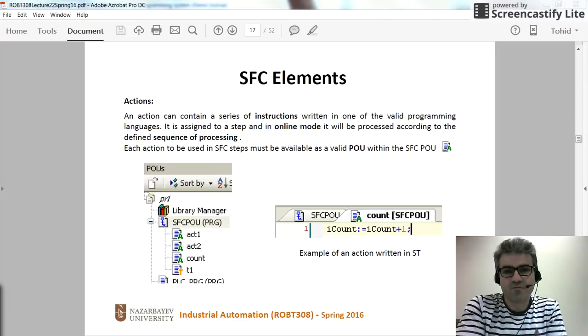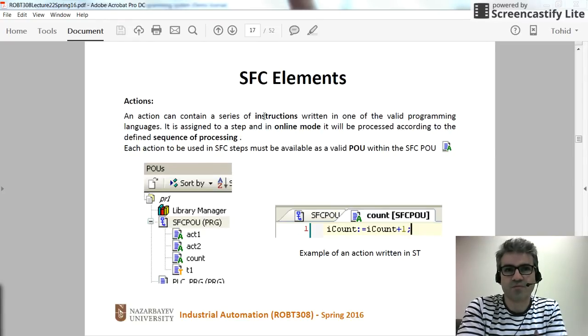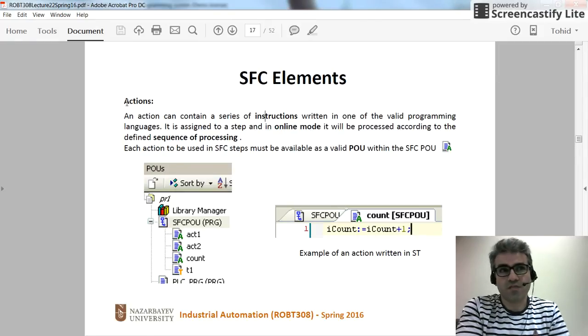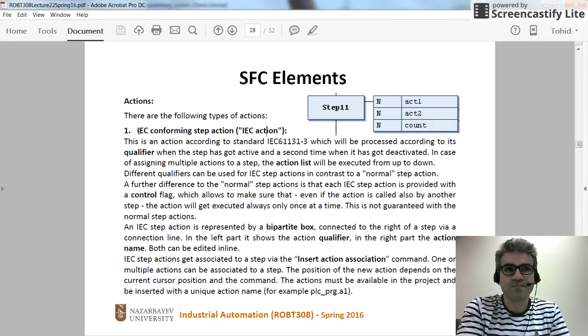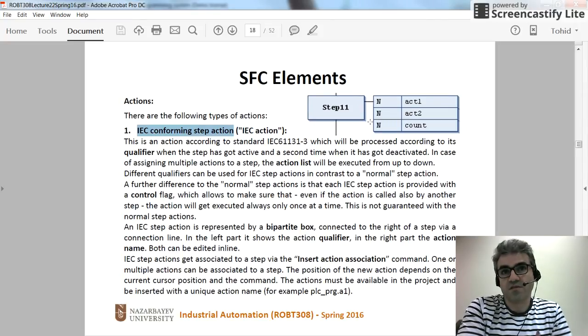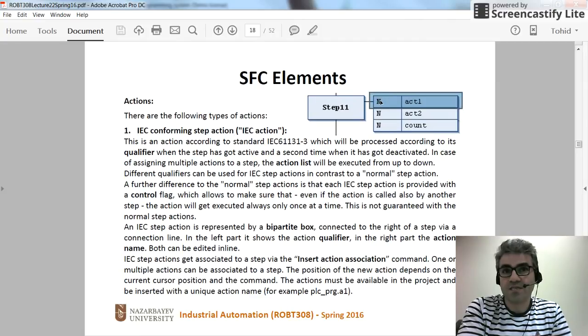Hi everyone. In this video I'm going to talk about the actions that we have in the SFC programming for PLCs. The actions can be categorized into two main categories. The first category is called IEC conforming step actions, which are the actions placed on the right hand side of the steps. Each action has two fields: one is called the qualifier and the other one is the name of the action. The qualifier can be N or some others, as I will show you later.